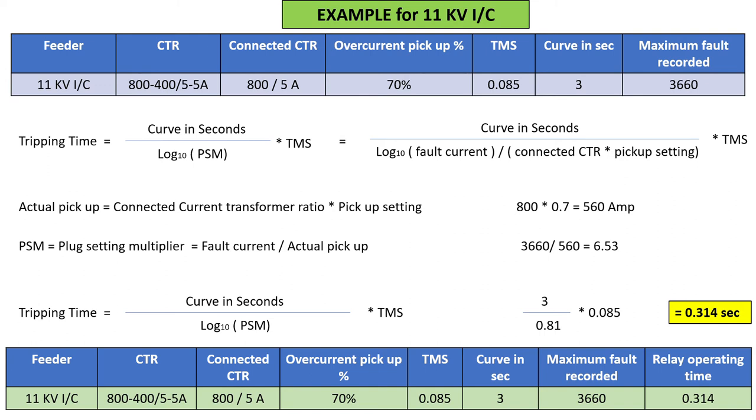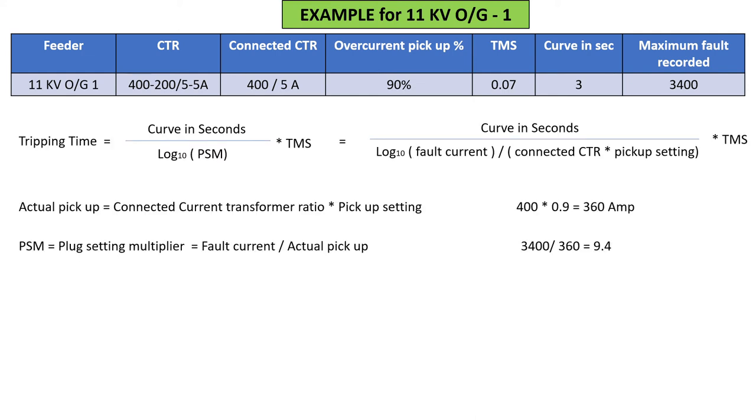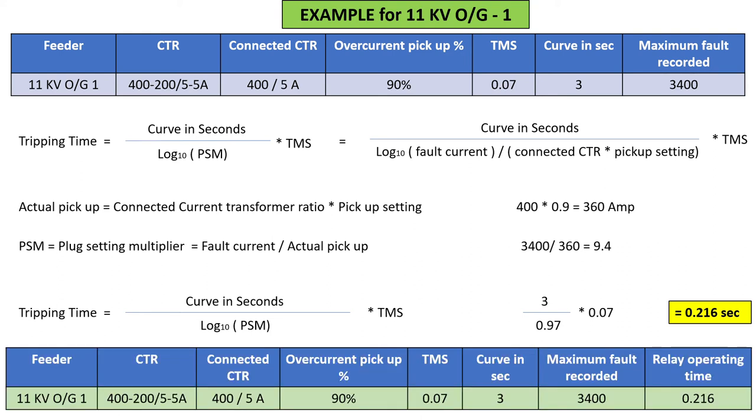Similarly, for 11 kV outgoing feeder one: CTR, pickup, TMS - fault current is different at 3400 A, rest of the process is the same. We found the pickup is 360 ampere and plug setting multiplier is 9.4, so tripping time comes out to be 0.216 seconds, about 216 milliseconds.